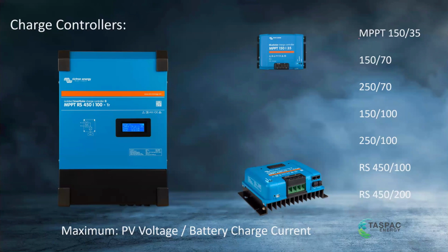MPPT means it's a maximum power point tracker, which you're probably familiar with from solar inverters. That's what deals with the solar. And the maximum open circuit voltage of the solar is 150 volts. The maximum charge current is 35 amps. So you see there, you've got MPPT 150/35. And that's the model number, which is great because it's so easy just to go, oh, it's a 150/35, cool. This is how many panels I can string out to it.